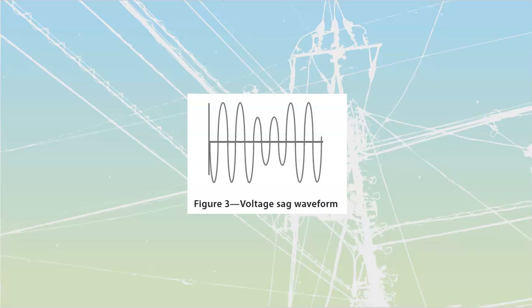Other types of electromechanical components are going to be held in magnetically. If I lose my value of voltage over here, if it drops too much, contactors, remember, they've got that spring inside that's trying to push that armature back out of there. If we lose this voltage, we're going to lose magnetic flux, which in some cases is going to be enough that those contactors are going to be able to release and go back.